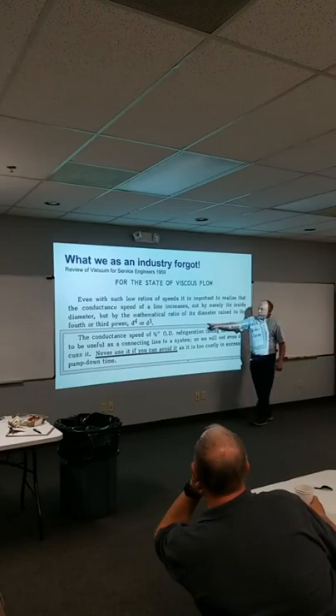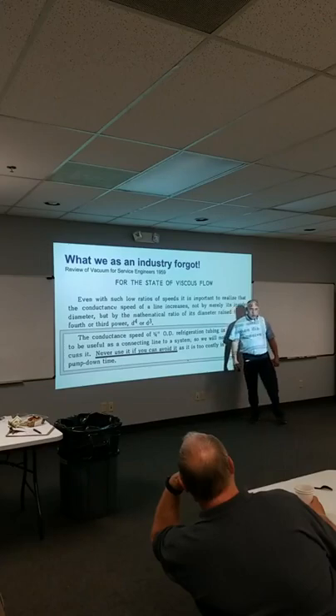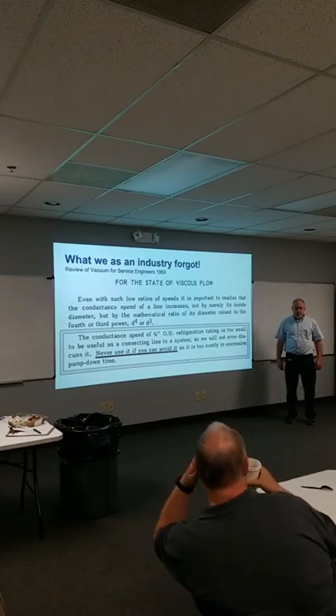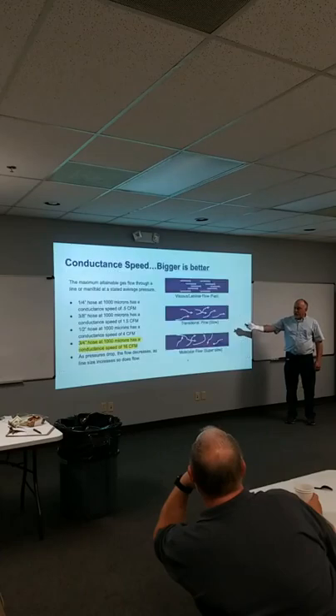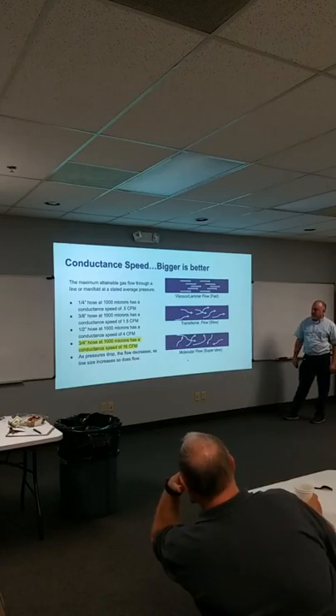this is why this matters. It's diameter to the 3rd or 4th power, okay? This is like the guy that tells you that when you tell him you need a 20-inch return, he goes, yeah, if I put 2 10s on, right? He doesn't quite understand diameters, and that's not the same thing. No. Okay? It's diameter to the 3rd or 4th power. So when we start increasing this hose size here, right, it goes up exponentially, okay? And as pressure drops, the flow decreases, and as line size increases, so does the flow.